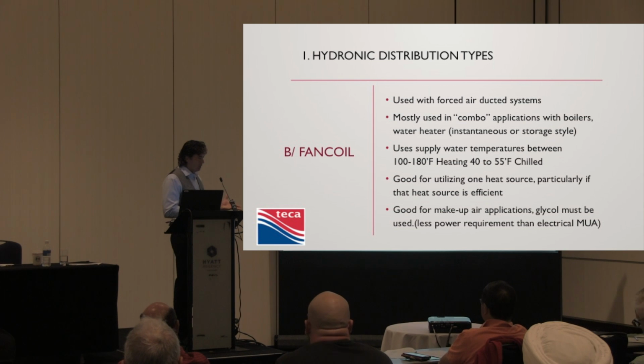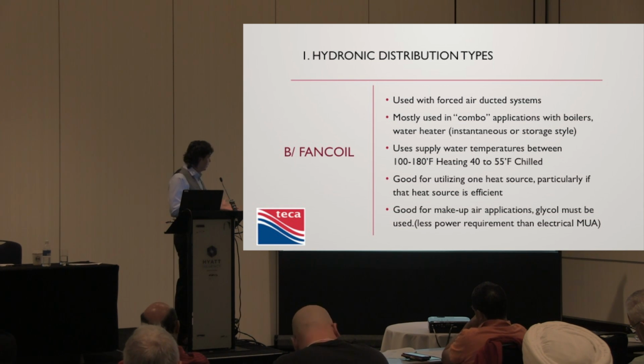So a fan coil is basically a box with a fan in it and a coil, a hot water coil. So what we're doing now is using the boiler or water heater or what have you, a combo system, and you circulate water to the fan coil, to the coil, and you turn on the fan, and away you go. You've got yourself a warm air, forced air system. So it's mostly used in applications with boilers or water heaters, instantaneous or otherwise.